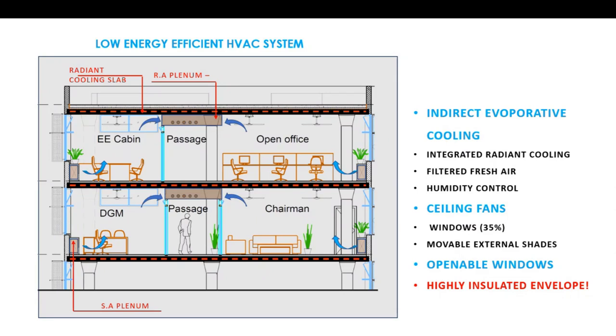You have external shading screens which can be moved. You have a roof terrace which is well insulated, insulated all around. You have the radiant cooling system buried in the slab, and don't forget the ceiling fans, which can be operated by the occupants close to them.